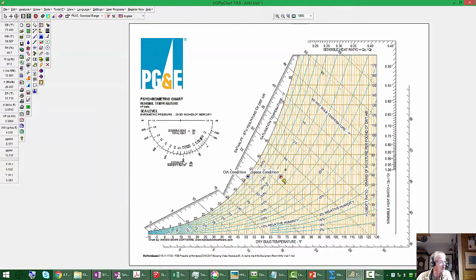So let's add a second point. So this will be the space condition. And the space condition is, we're going to assume it's 72, and we're going to assume the specific humidity is the same as the outdoor air. So specific humidity is what was it? W, 58.2 grains of moisture per pound of dry air. So there's where a space condition probably is. It could even be a little up this way because of the moisture.